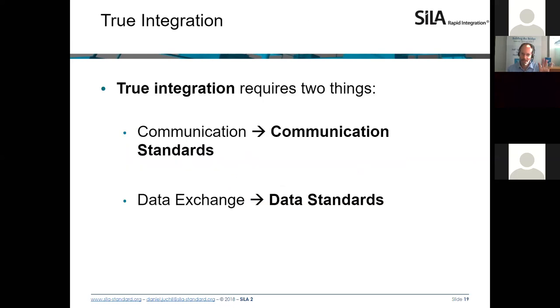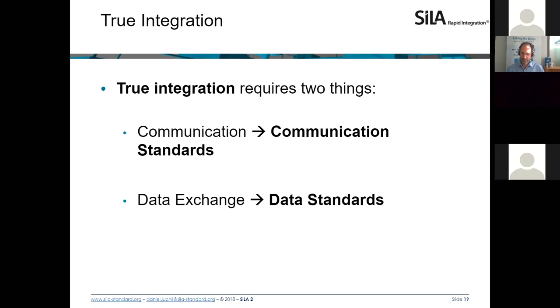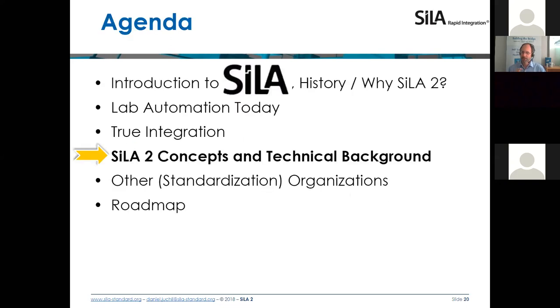As a consequence, integration requires both communication standards and data standards. For the communication layer we talk about SiLA — SiLA is the communication standard to make lab systems interoperable. Once you communicate to a system, for example a spectrophotometer, you get back the spectrum and have to interpret it — this is where AnIML comes in, taking the data part and data standardization. SiLA and AnIML go together very well, and the organizations share very similar models of licensing and openness.